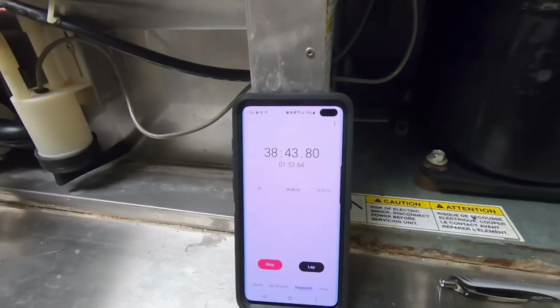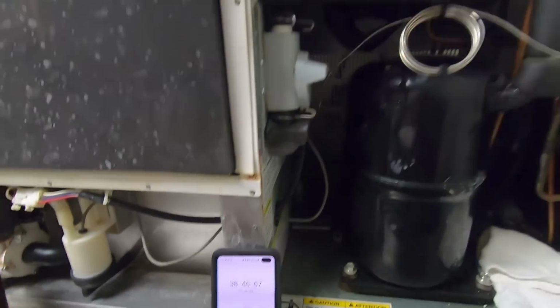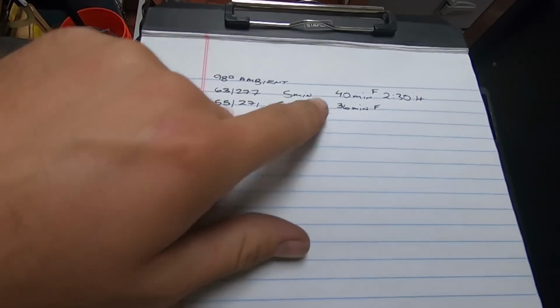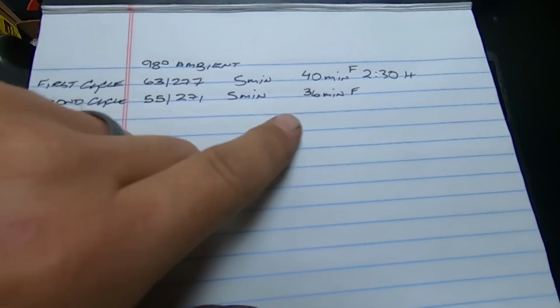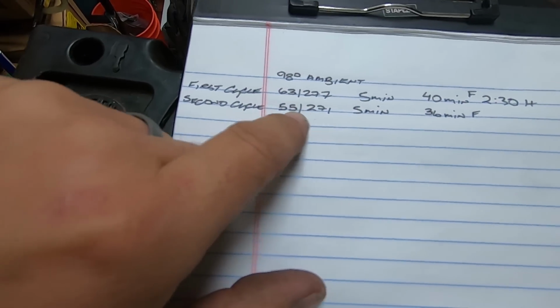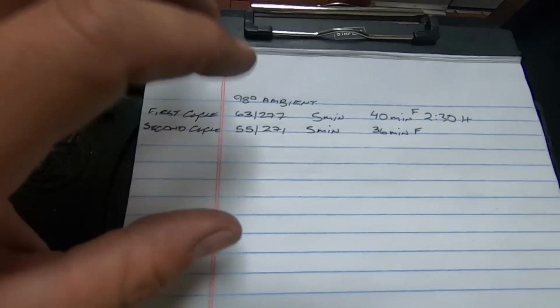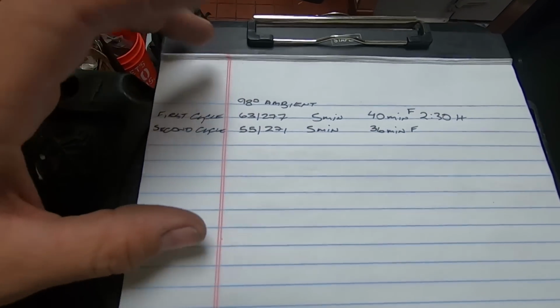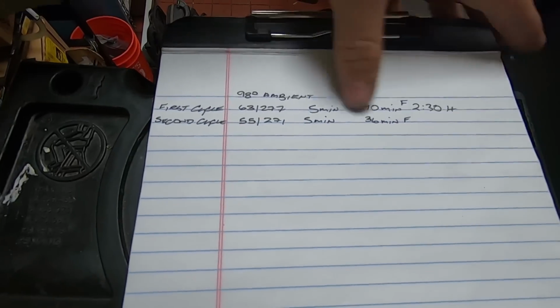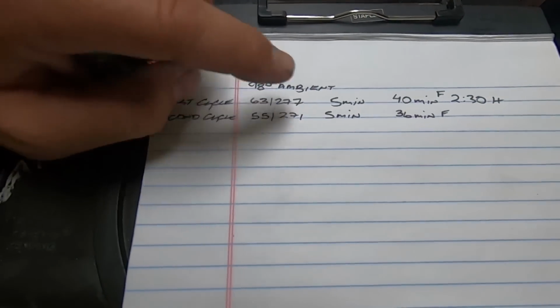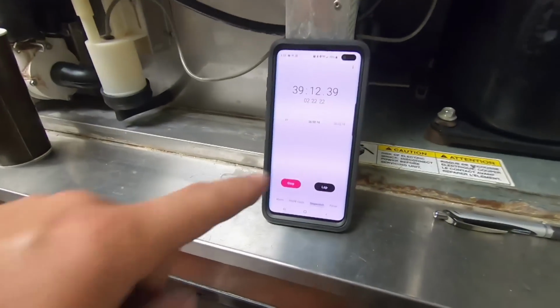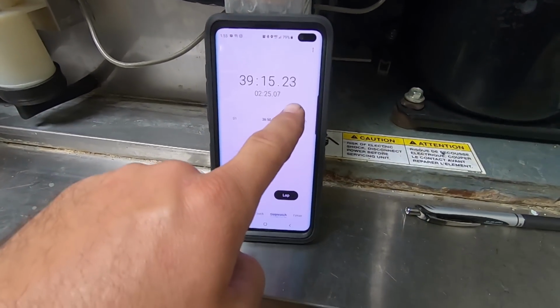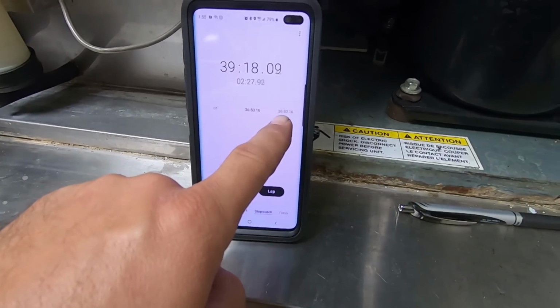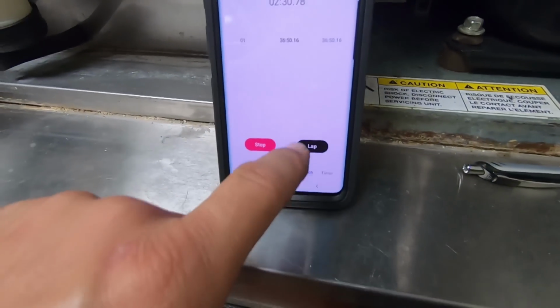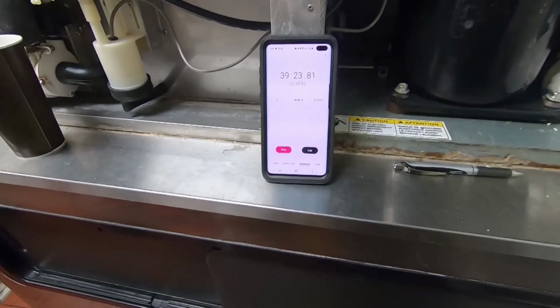All right, we just finished our second freeze cycle, and I'm waiting for the harvest to complete. Everything's looking good. The timing is looking a lot better. So we had a 36-minute freeze cycle. The refrigerant pressures were pretty much on point with what the manufacturer says they should be. Oftentimes when you start these up after it being off for so long, you'll run the first cycle, and you almost want to wipe it out of the picture and just pay attention to the second and third cycle. So we're just waiting for this. What I do is I hit lap, so that tells me where my cycle's at, 36.5, and then I'll hit lap again when the harvest stops.